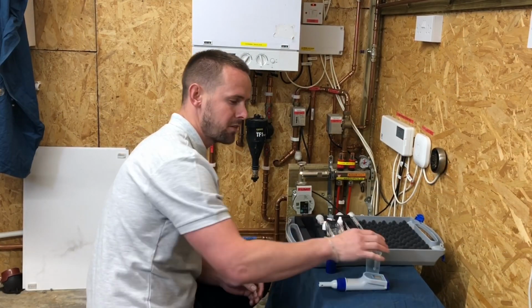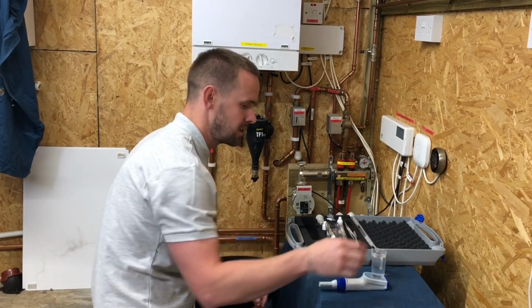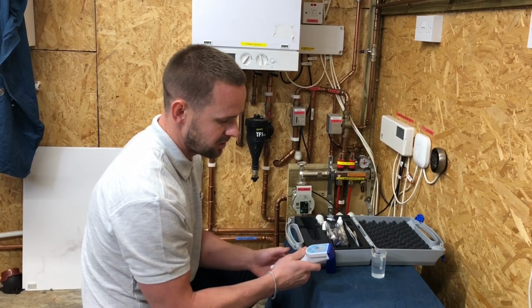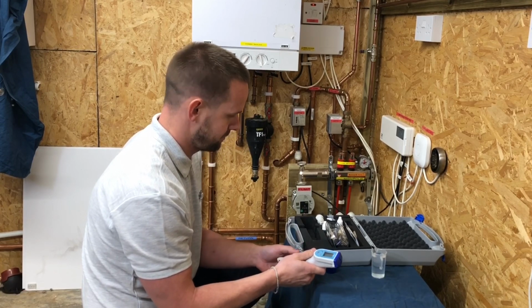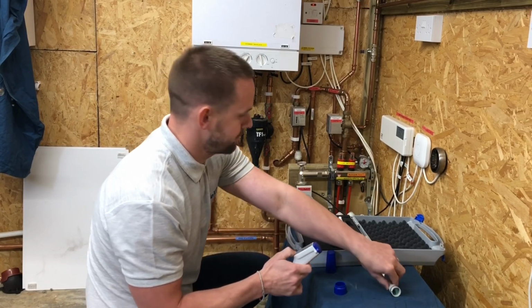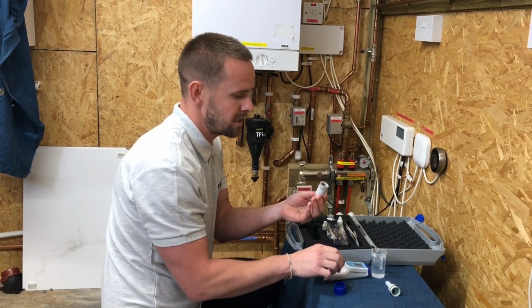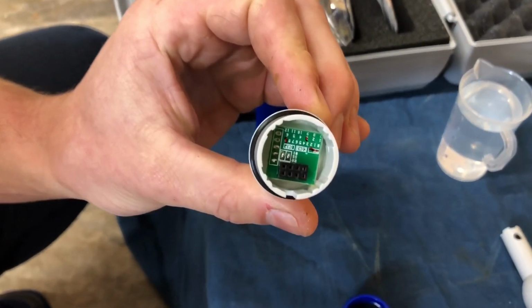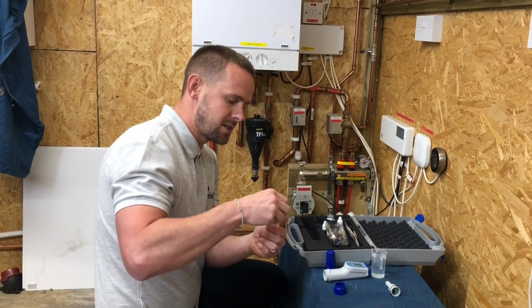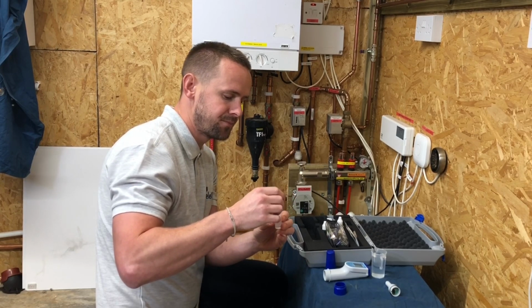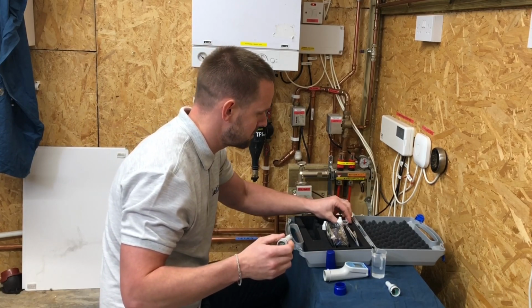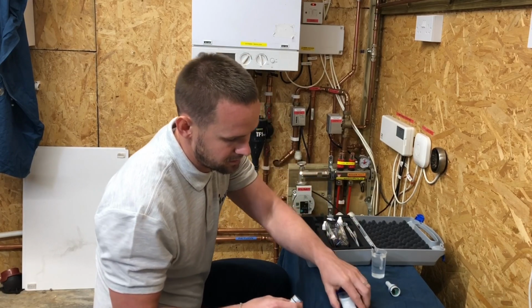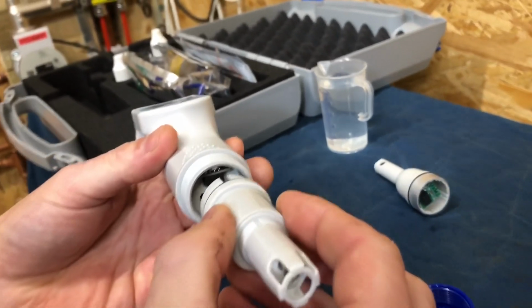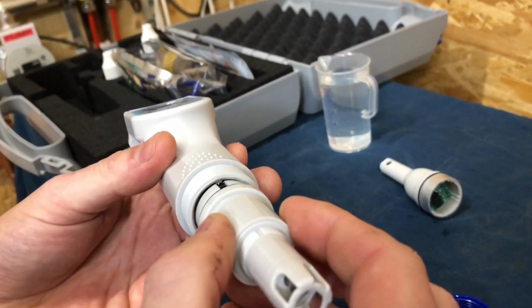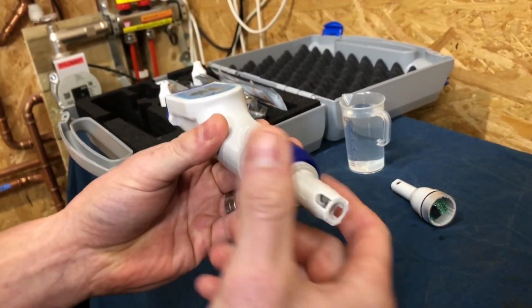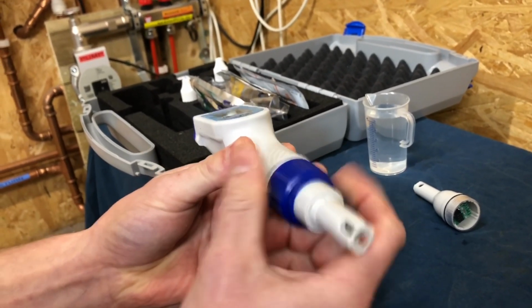So now we're going to test the pH. What I've done is I've just changed the water over in the test beaker so we don't have any contaminants. So very simply, just turn this anti-clockwise. I'm going to pull the probe out. We're going to get our new probe. So this one does the pH. So just on top we've got the little circuit board, and you'll see this is where we put the pins in. Untwist the base. Just be careful because there is some electrolyte fluid in there. Okay, so that just keeps the probe moist at all times. And we're going to simply line up the bottom with the pins. Push that in. And then tighten it up, and then we're good to go.